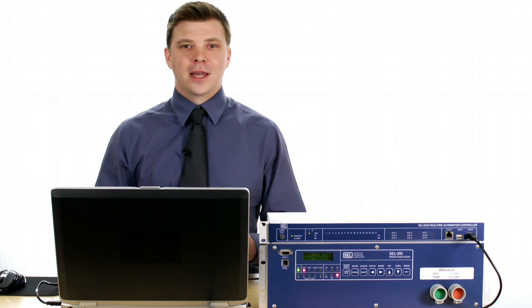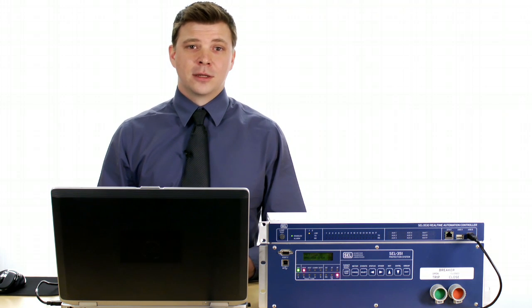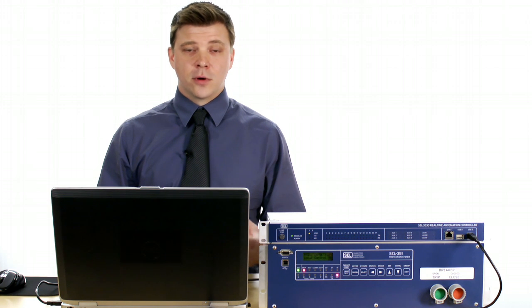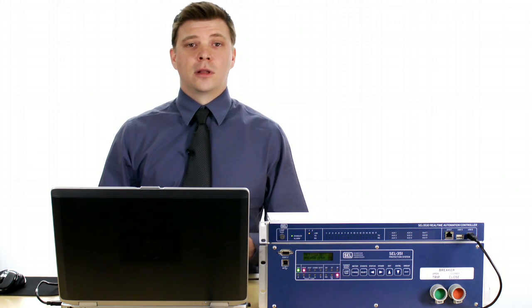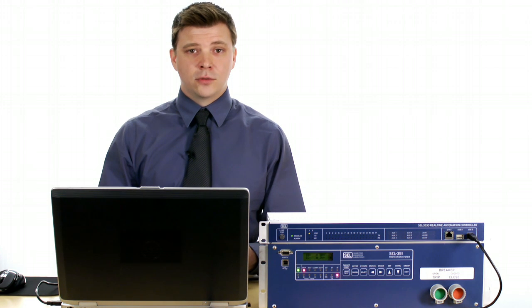Okay, so we successfully added a DNP client to our project. We've added a few DNP points to pull from our 351 relay. We went online with the project, downloaded that project to the RTAC, checked to make sure our communication, our configuration was valid, and sent a control to the relay. We did this all in a couple easy steps.